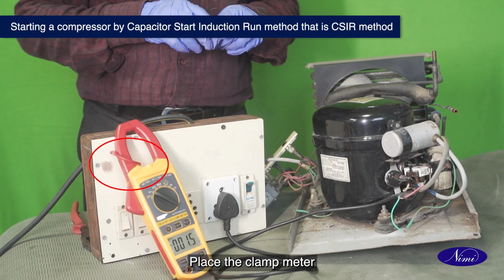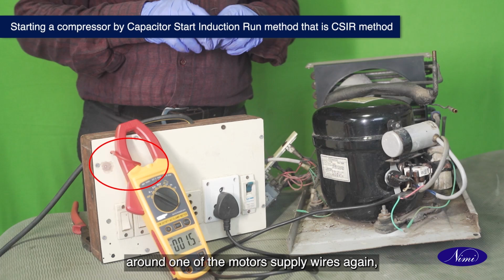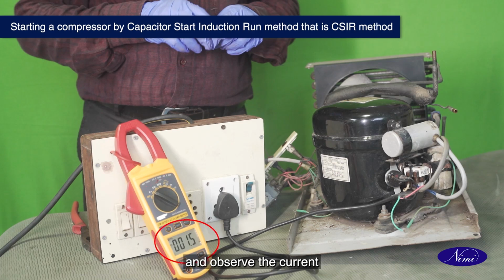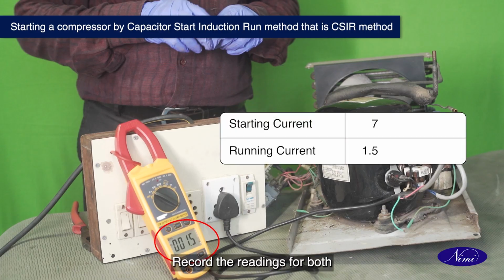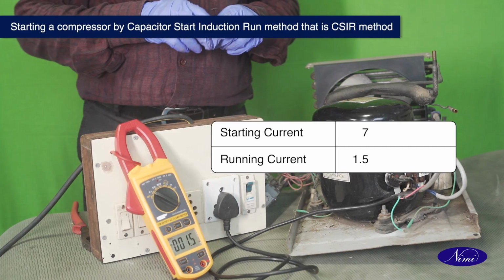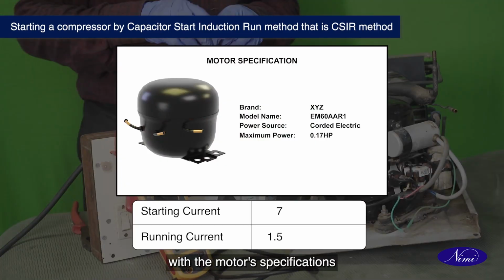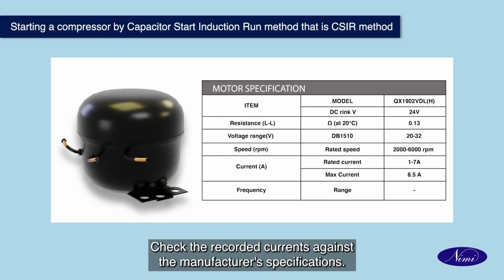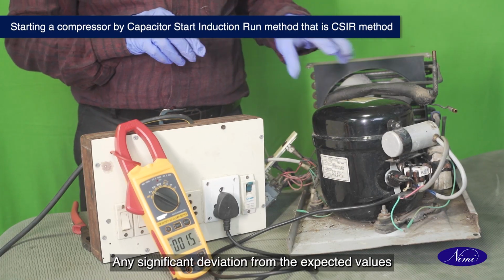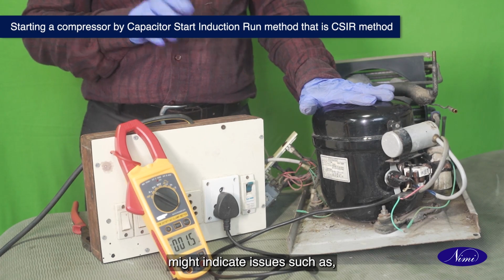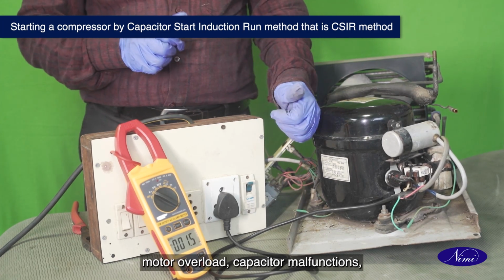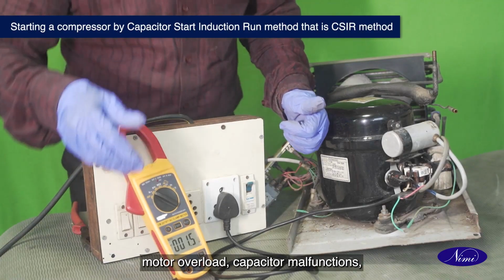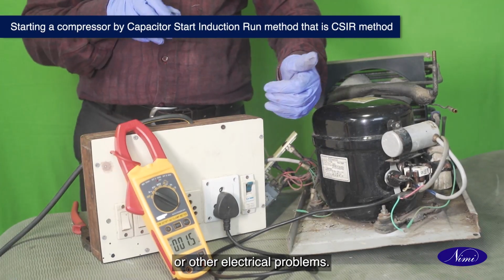Place the clamp meter around one of the motor's supply wires again and observe the current while the motor operates normally. Record the readings for both starting and running currents. Compare these readings with the motor's specifications or recommended values. Check the recorded currents against the manufacturer's specifications. Any significant deviation from the expected values might indicate issues such as motor overload, capacitor malfunctions, or other electrical problems.